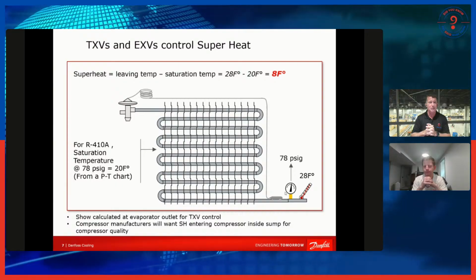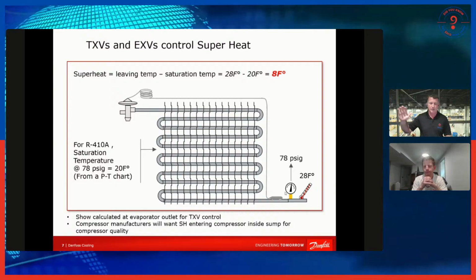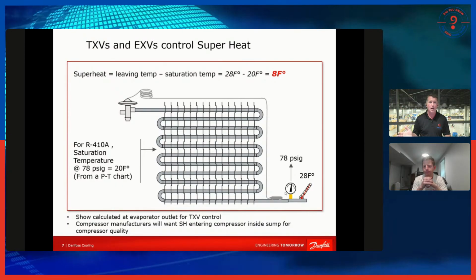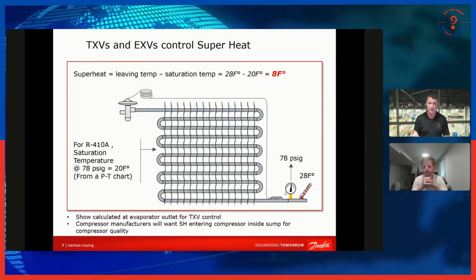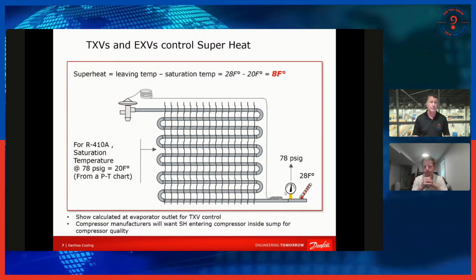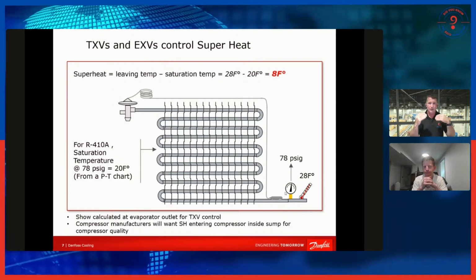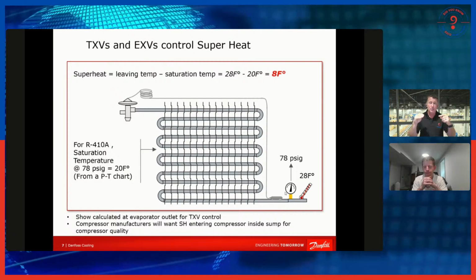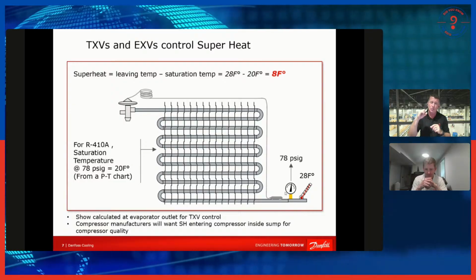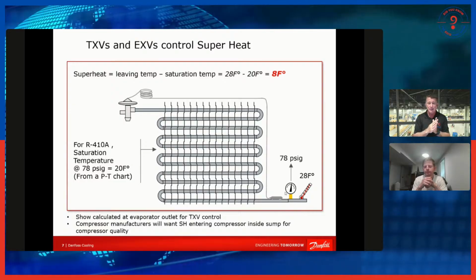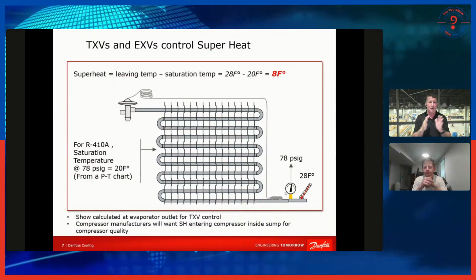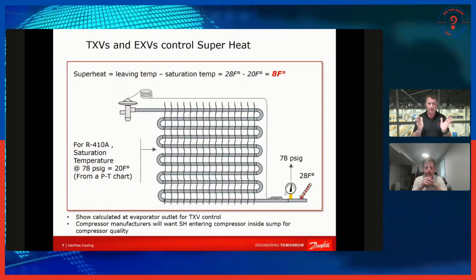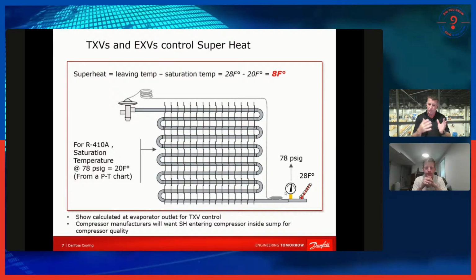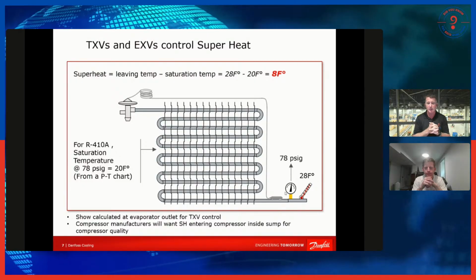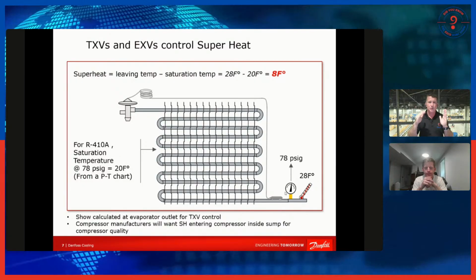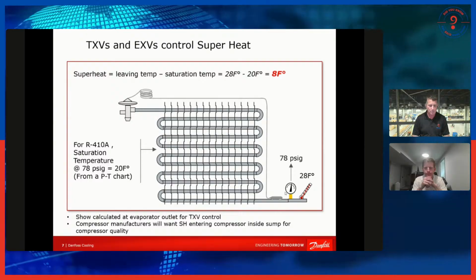As we move into 454B and a variety of other 400 series refrigerants, whether you're working in air conditioning or refrigeration, we have to be aware of the variations of that glide between those boiling points. It can be critical for the placement of that bulb. And in many cases it widens that window of operation for controlling superheat. And that's the reason we're going to start seeing a lot more electronic expansion valves, so we can start fine tuning and programming these things for optimal operation.